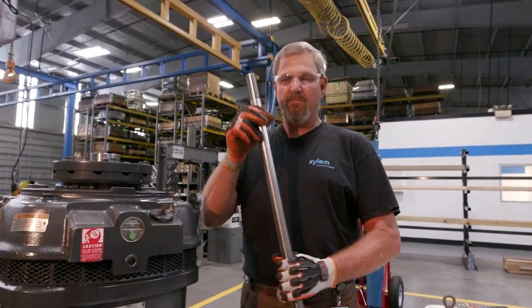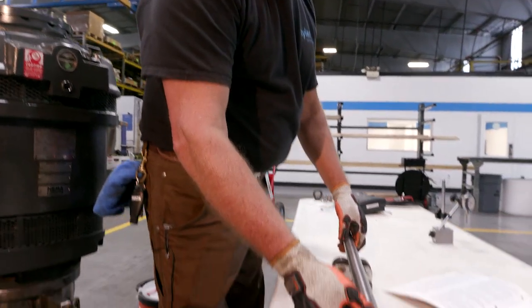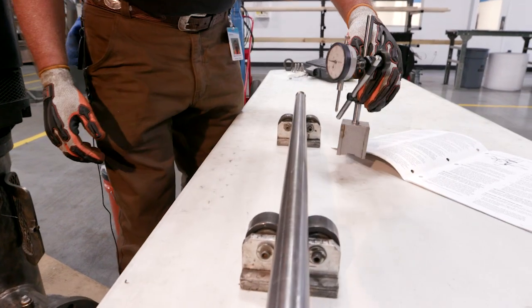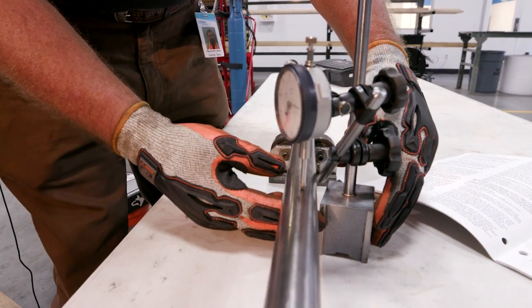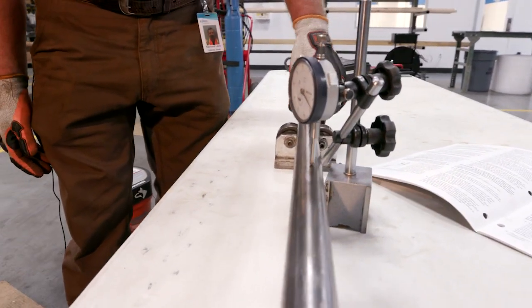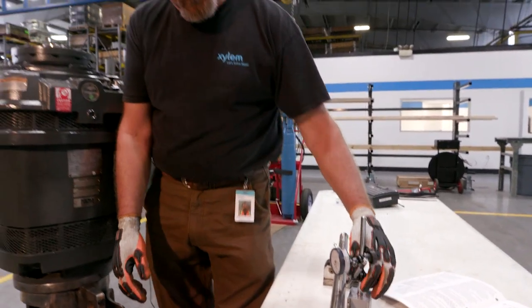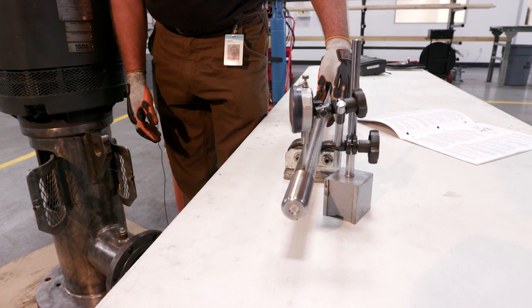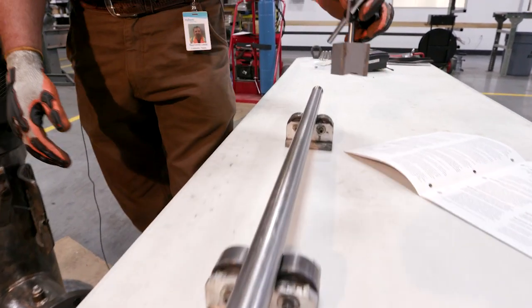Our next step is to check our head shaft to make sure it's straight. We use rollers at the factory and in the field. We take an indicator and adjust it within two thousandths. As we check our shaft, we turn it and roll it. If it's good, we take it to the next step — check each end — and make sure it's straight and ready for installation.